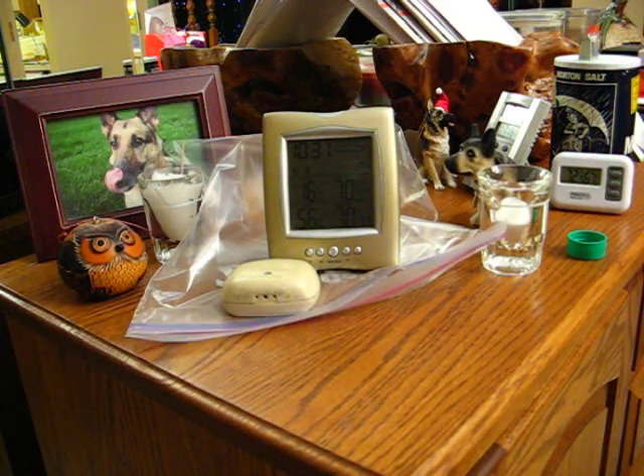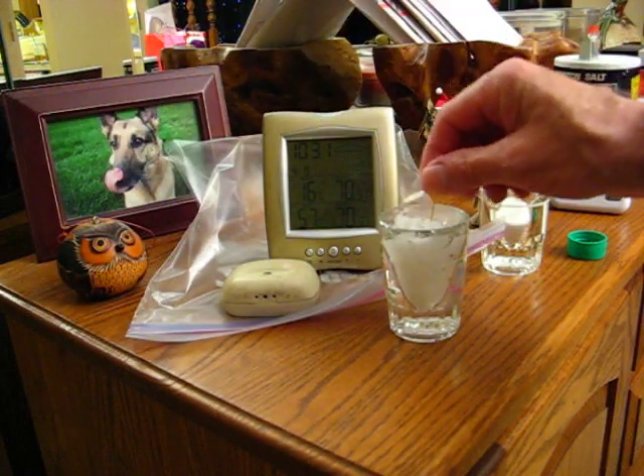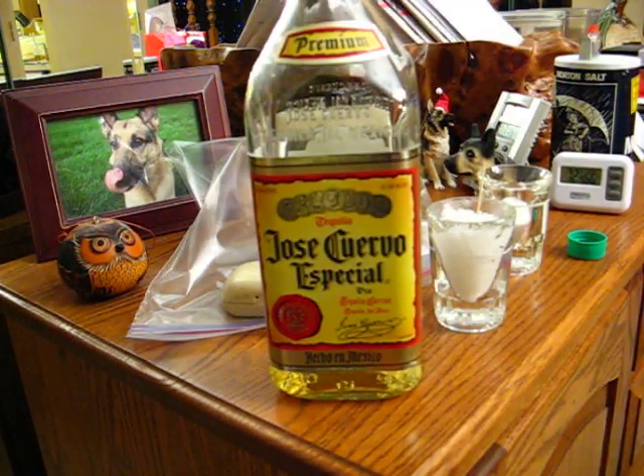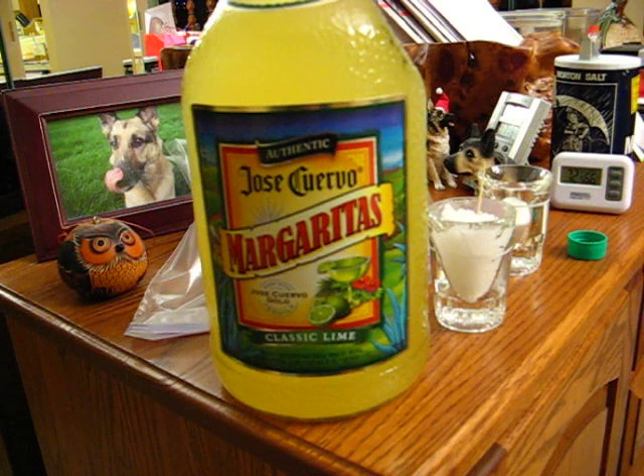If you have an analog hygrometer, you can actually calibrate it using this method. And when you're done with the salt solution, you could pour it into a little dish and do some shots or make some margaritas — after all, you've just completed a very intense, ambitious experiment that took eight hours. So congratulate yourself and have a nice time. Bye!